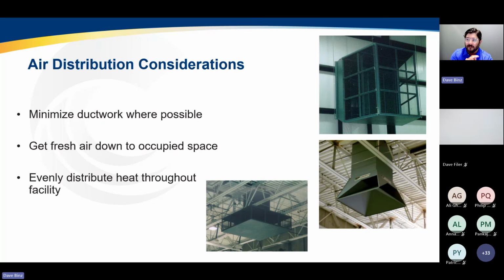And secondly is air distribution. Even on the ventilation side, most manufacturers of industrial spaces, they want to keep that indoor space as free of equipment and ductwork as possible. They want to have this open sandbox inside the space, because they're moving lines, they're moving equipment, they're moving racks, and ductwork that is used to essentially help us get distribution becomes now a challenge for how they want to be able to modify their building for future product needs, future operation needs. So we try to minimize that ductwork where possible, and we want to provide that fresh air, that ventilation into the building without having to really move any equipment or racking around as possible.